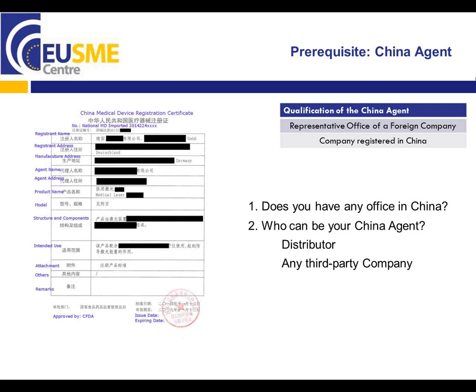Okay, good. So now we're talking about the prerequisite of a China agent. On the left of the slide, you're going to see an example of the new medical device registration certificate. Here you can see that on the top is the manufacturer's name and address, and the OEM if you have one. Then comes the China agent's name and address, and that will be really important for you. You will still be the holder of the medical device certificate. You should have a China agent, and they are listed on the certificate. They have to help you during communication, during the registration process, and also afterwards for marketing, to communicate with the CFDA, and also take care of all the legal responsibilities for the product quality.